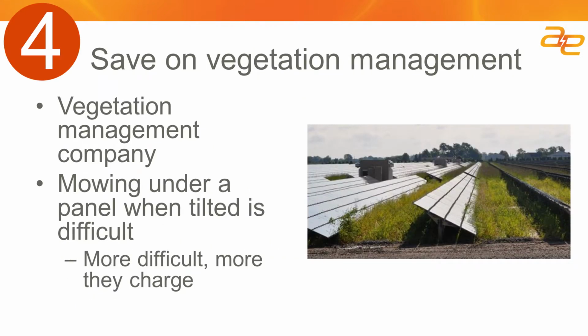Bullet 4: here in the southeast, vegetation is a persistent problem on solar sites, and I see companies willing to come out and do vegetation control—basically mowing the lawn. With fixed sites it's more of a challenge, because you've got an edge of module that may be specified to be no less than 18 inches from the ground, but the structure underneath leaves less clearance than that, making it difficult to get mowing equipment under.